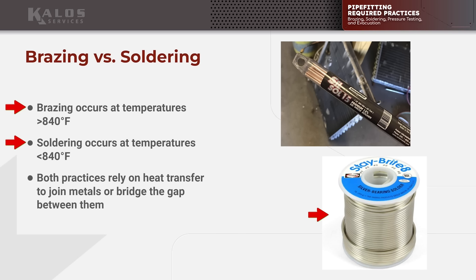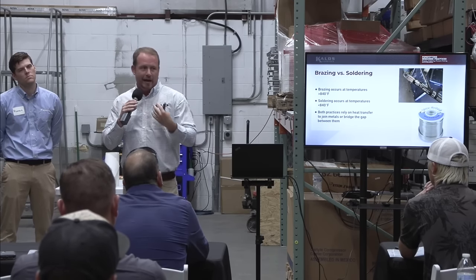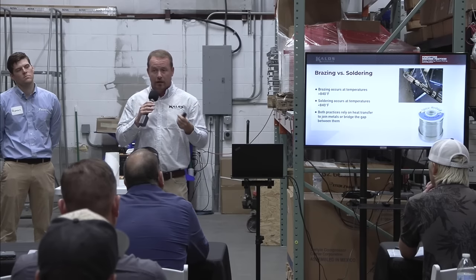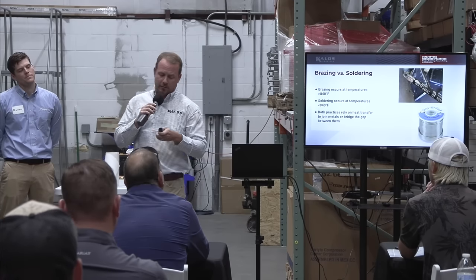There are some products out there, like Stay-Brite 8, where some folks do actually solder, but in the refrigeration world that's not standard at all. I use the word 'alloy' because alloy is whatever joining material we're using, and there are a lot of different alloys. We typically use a silver phosphorus brazing alloy when we're working copper to copper, but we'll also talk about some dissimilar metals.